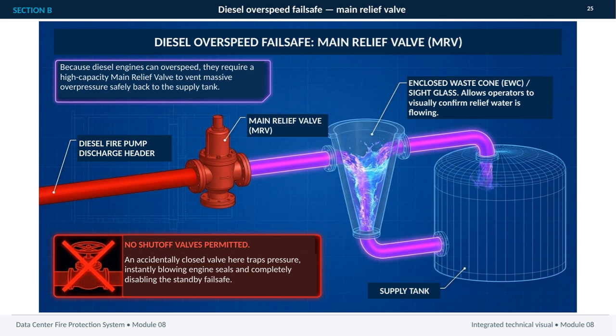The most critical installation rule is no shutoff valves permitted. If a valve in this path is accidentally closed, pressure can become trapped almost immediately. The resulting pressure can blow engine seals and disable the very failsafe intended to protect the pump. So, when inspecting this system, I would confirm the MRV's connection to the discharge header, the return path to the supply tank, visible flow at the sight glass, and an uninterrupted, non-isolatable relief path.